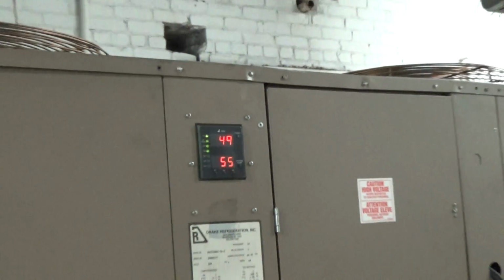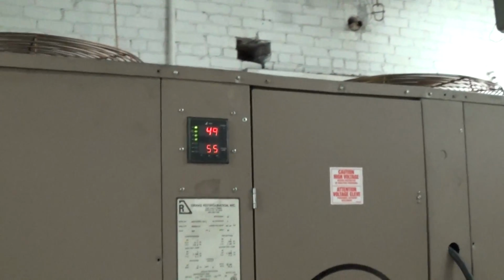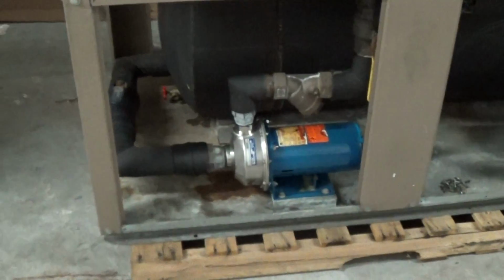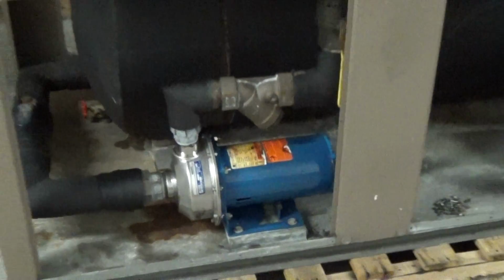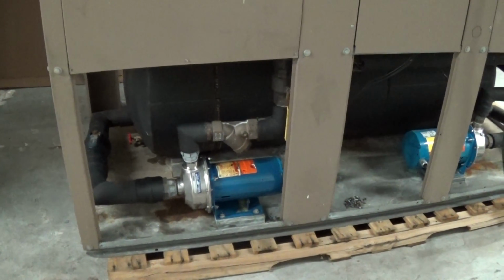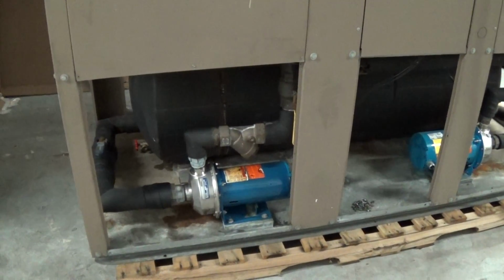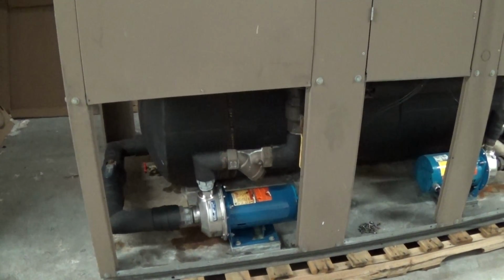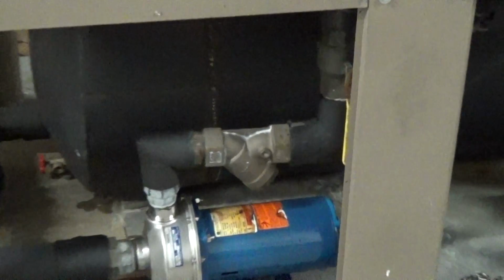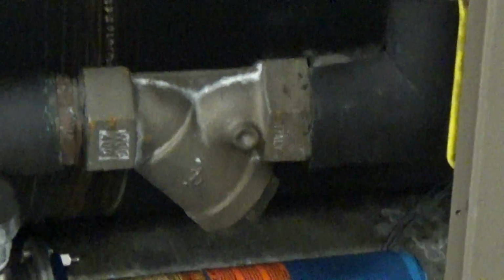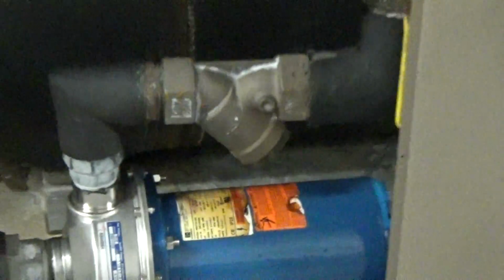An example of why you'd get a low flow alarm sometimes would be if you're either running at so cold of a temperature you're actually starting to freeze up inside the evaporator, or if your Y strainer has gotten clogged or dirty, restricting the flow.